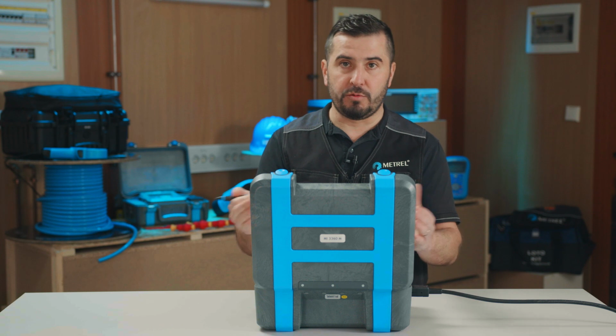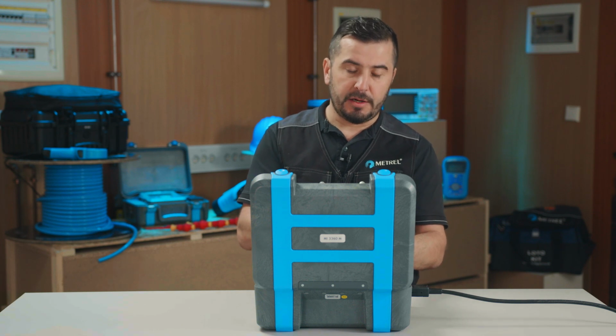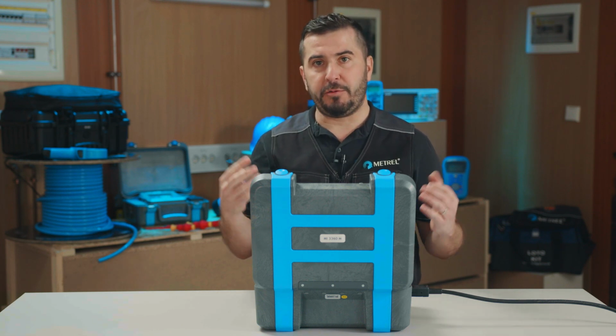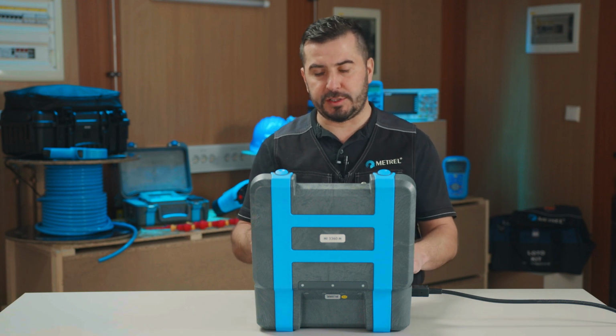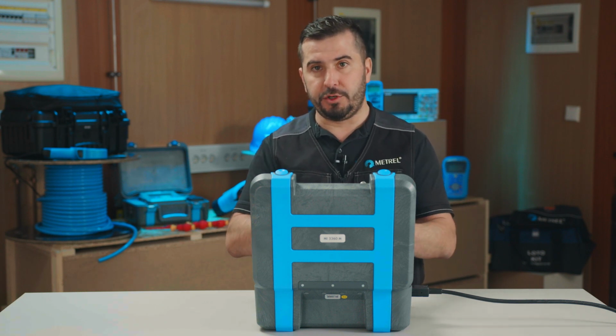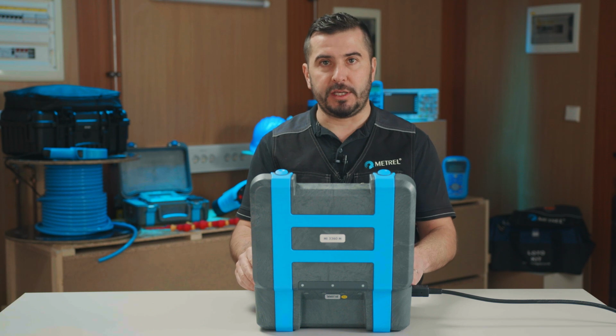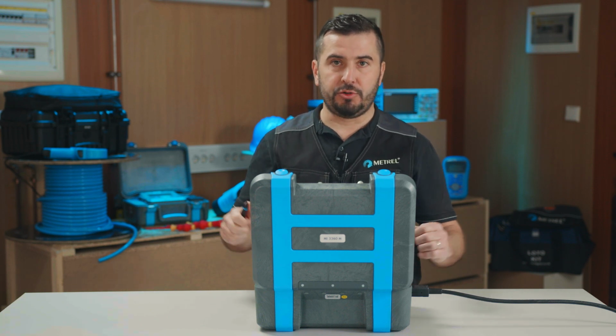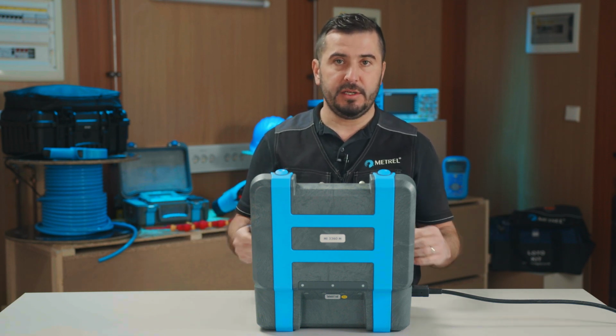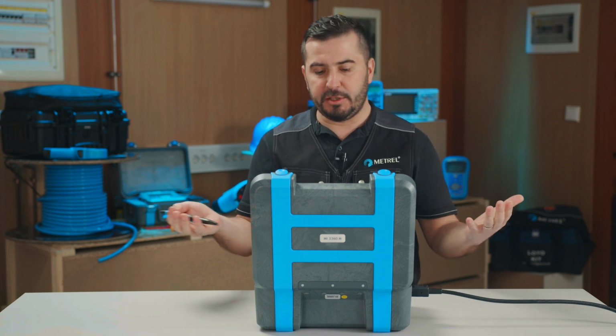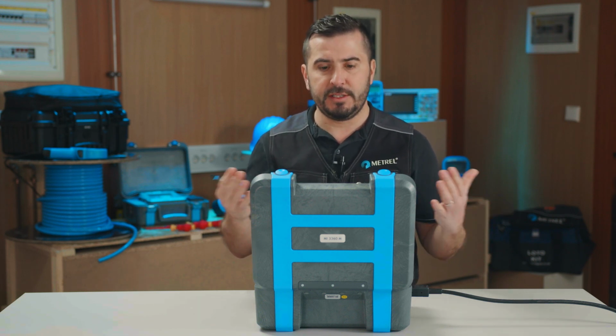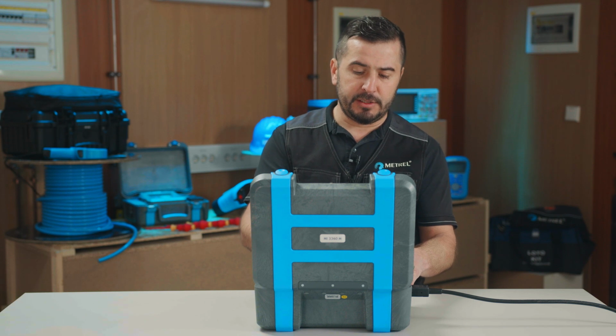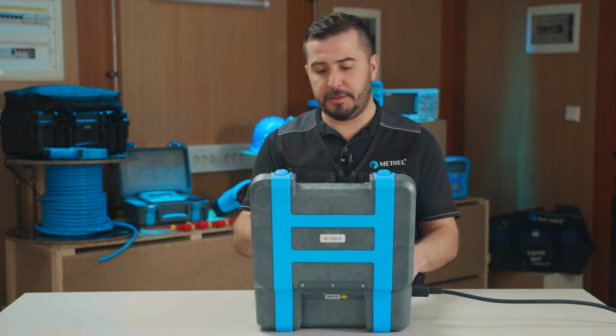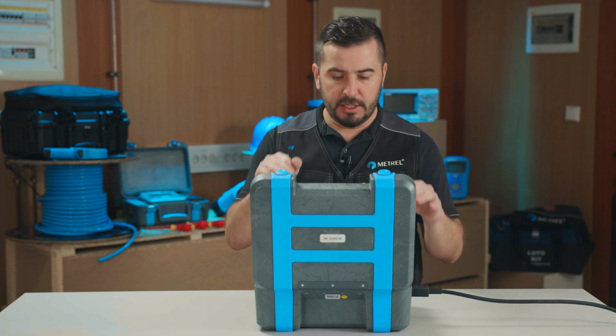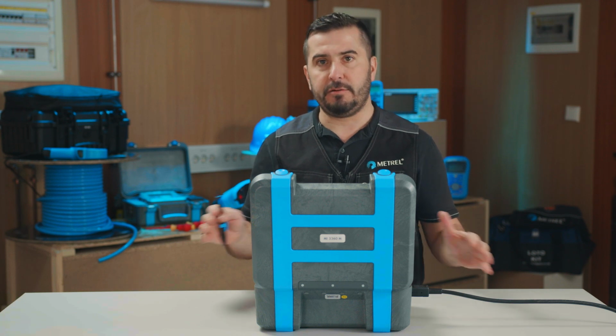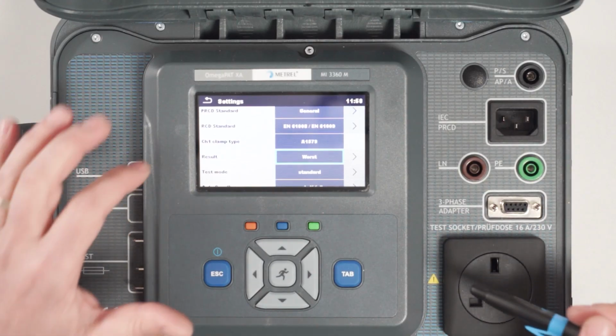If we put it on the worst, it is again very good feature, but when we are measuring leakages, or even earth continuity on extension leads, for example, because if it is set to worst, we have to bend cables, and during bending of these cables we are not constantly looking on the display, and if the device is set to worst, the worst result will be displayed on the instrument itself once the measurement is finished.